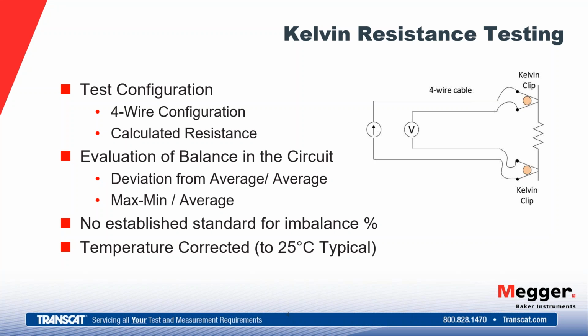So we're going to supply the current source so we know what that is. We're going to measure the voltage drop across that resistor, and then using Ohm's law, we calculate the resistance of that circuit. So we're going to get 3 values from that, from lead 1 to 2, 2 to 3, and 3 to 1. So we get our phase-to-phase resistance for each of the 3 combinations. And then to evaluate that, the test is going to look at the balance of that circuit.